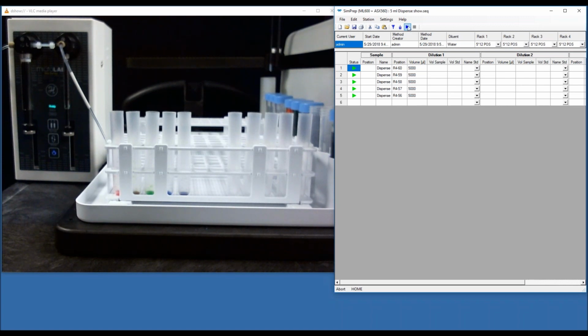So what I've set up here is just a little dispense protocol, and then I'll open up a second sequence for dilution. There are a few drops of some brightly colored liquids in the bottom of those tubes to hopefully provide a better visual as it dispenses. So the first thing it does is it always starts with an initialization to make sure that the system's communicating appropriately, and now it's doing its first rinse. This essentially serves as a prime cycle to make sure that you have fresh diluent in the system for when you actually start running your samples.